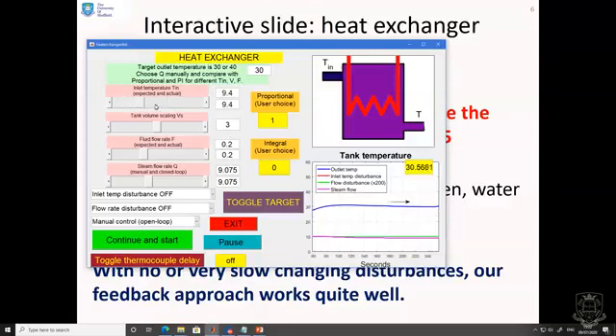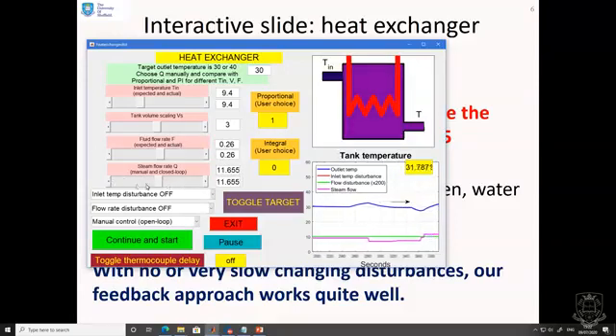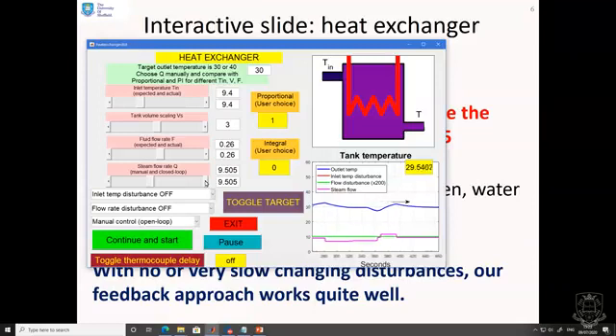Now, what if we get some form of disturbance? So the inlet temperature changes and, oh, it's going way too hot now. Let's reduce the steam flow. You can see very quickly, I can start bringing it back to where I want it to be. I can change other disturbances. What if the flow rate through the thing changes? Now I've made it a lot bigger. I need much more steam. And you see very quickly, I observe what's happening and I make a change. This is what humans do. They observe what's happening and they say, do I need to increase or decrease? And how much do I need to do it? You can see we can manage to control very effectively.